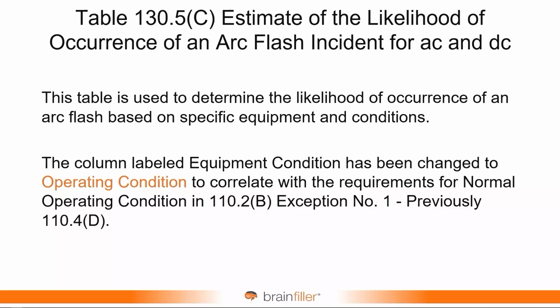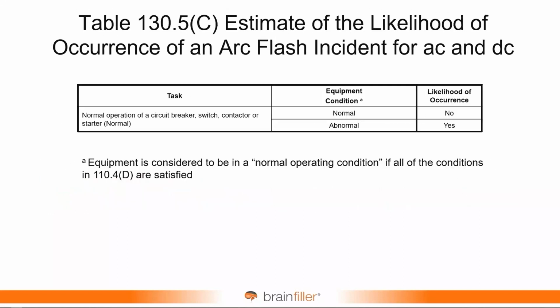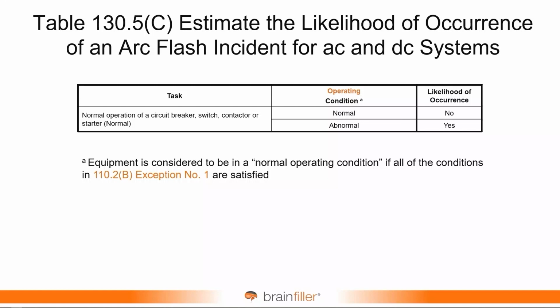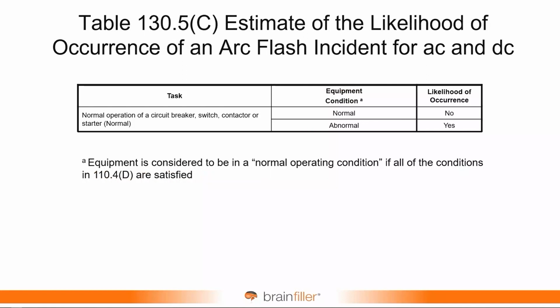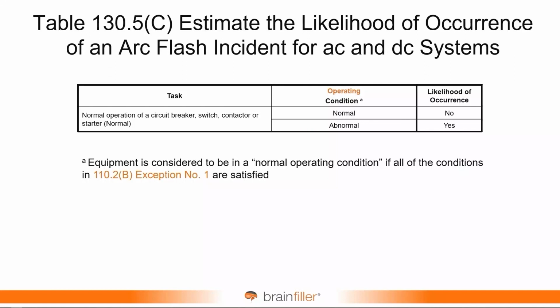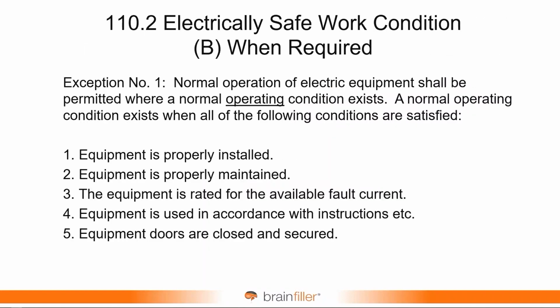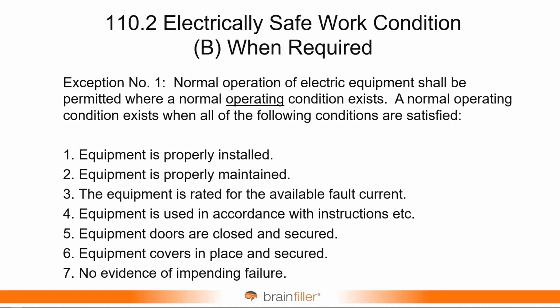Moving ahead, table 130.5(C), estimate of the likelihood of occurrence of an arc flash incident for AC and DC. Just some language change. This was changed to operating condition, just to coordinate with the changes that were made in 110. So this is now estimate the likelihood of occurrence, and the language change is from equipment condition to operating condition, and the reference was also changed because of the renumbering in 110. And this is simply referencing these 7 conditions that we were already discussing.